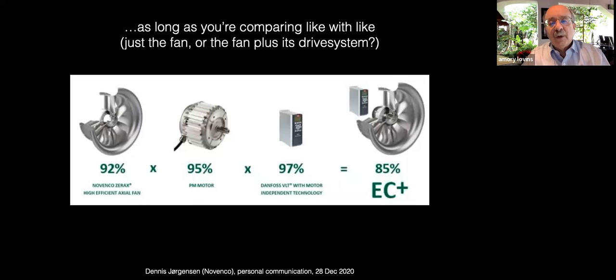So a 92% efficient Novenco ZerAx fan might mean 85% efficiency once you include the losses in the motor and the inverter. It's the power electronics that drives the motor. All these components do keep improving. Electric race car motors can be 97, 98% efficient. Their inverters 98 or 99% efficient. So if we use those in this case with the fan, we'd raise its system efficiency to 87 to 89%.